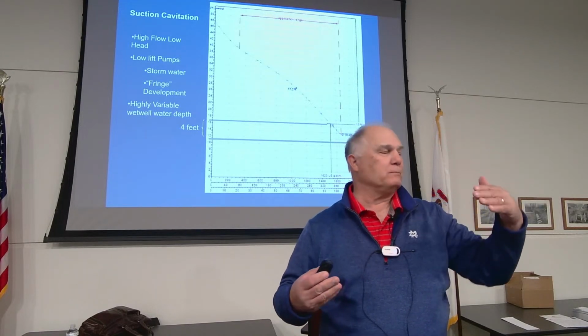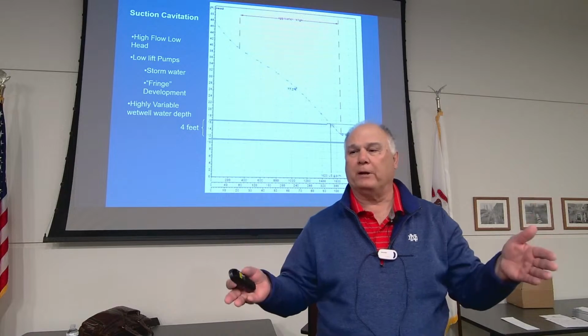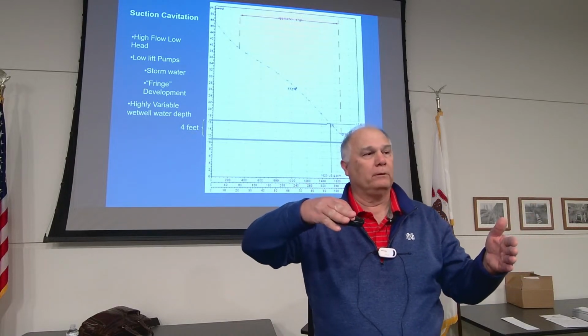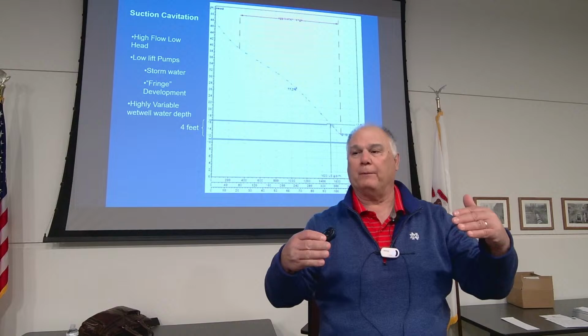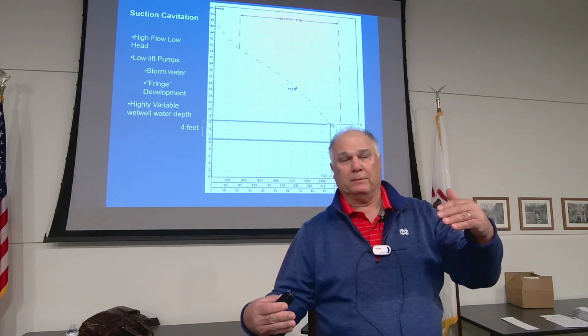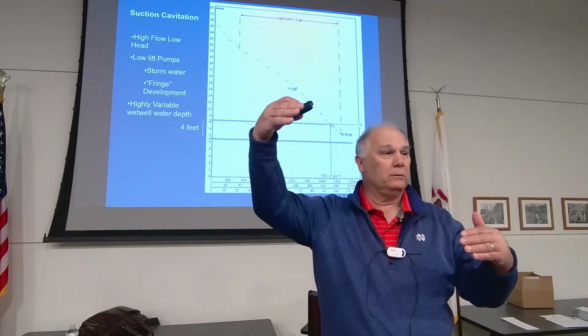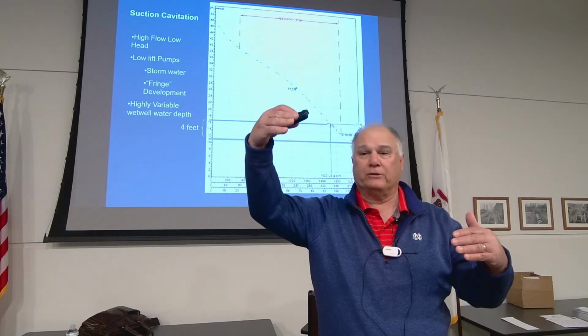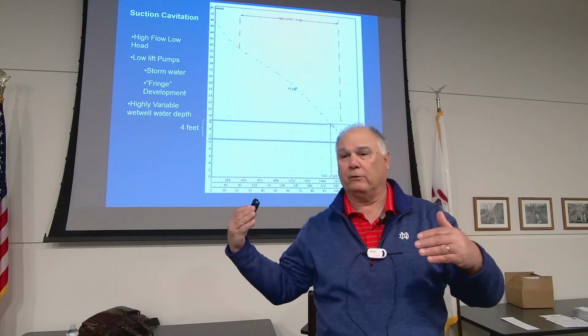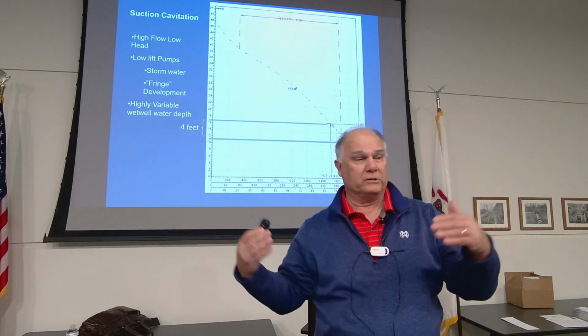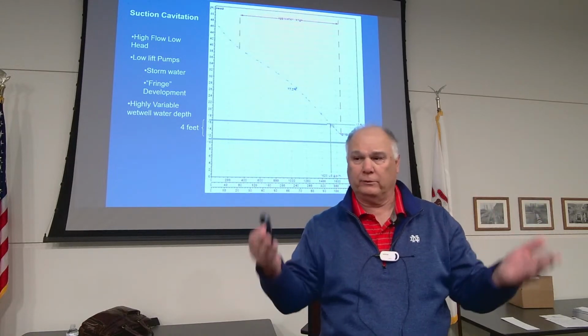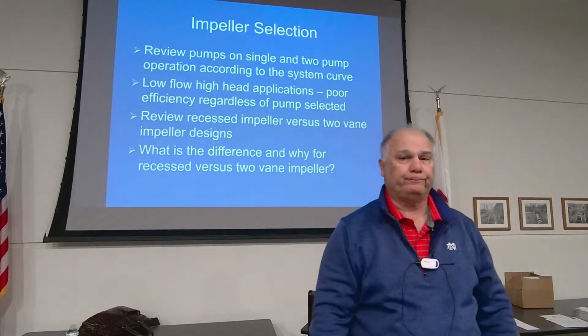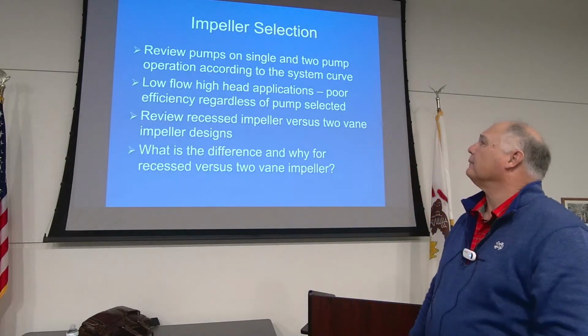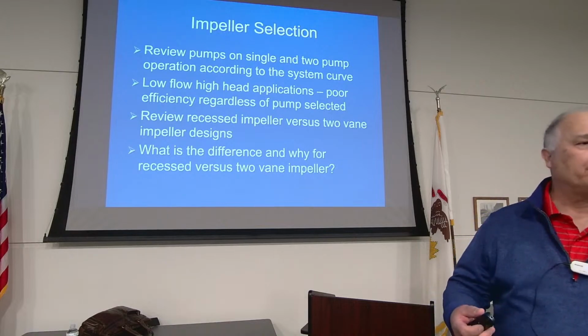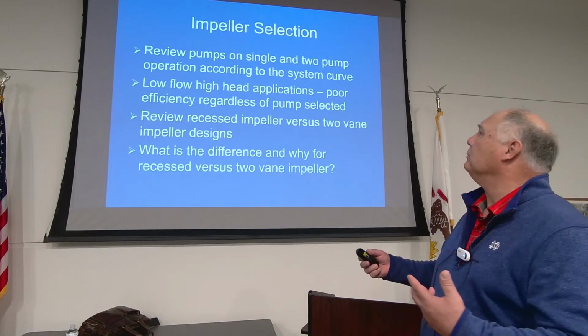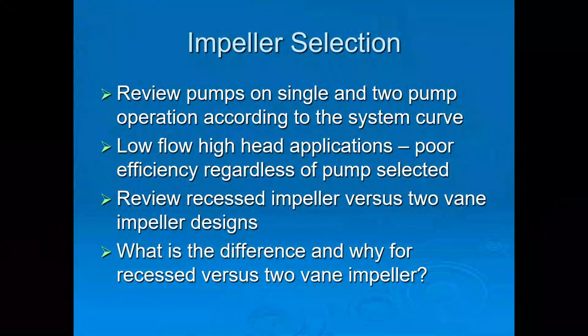So what happens is most engineers, these are all slow operating pumps, they have a very flat pump curve. Most engineers say, all right, we want to pump at this elevation, but they ignore the elevation up top. When they ignore that, we slide out to the right, or we have lower static, because the static does change on those. That gets to be a big issue. So when we review pumps, we review 1 and 2 pumps in operation.